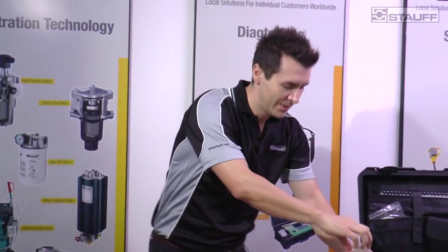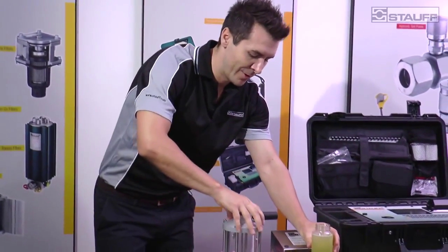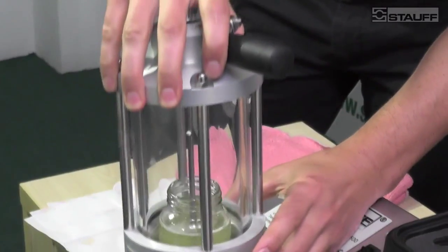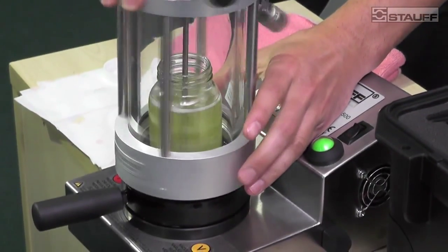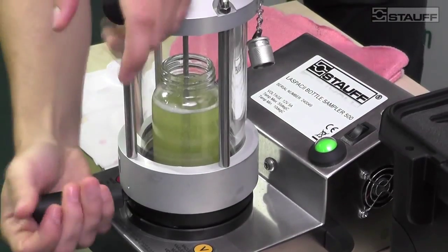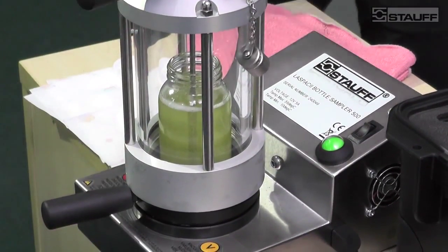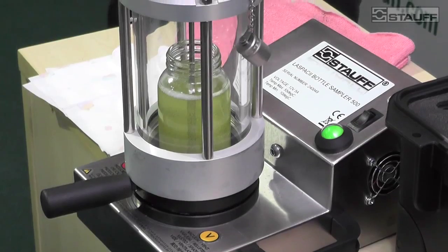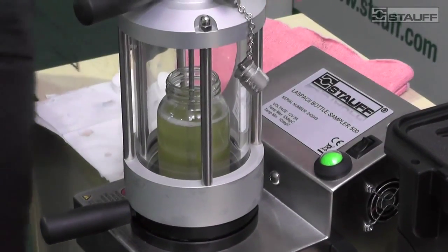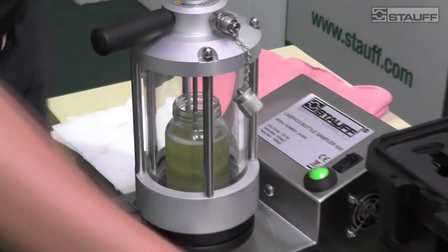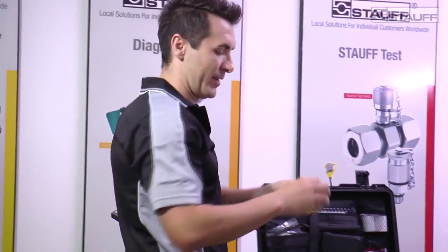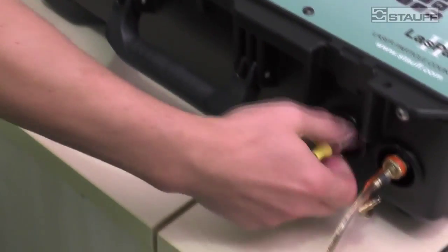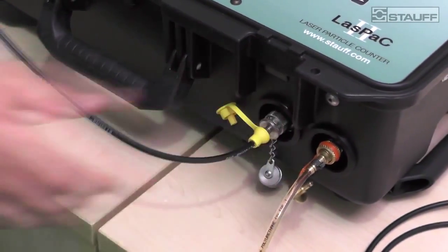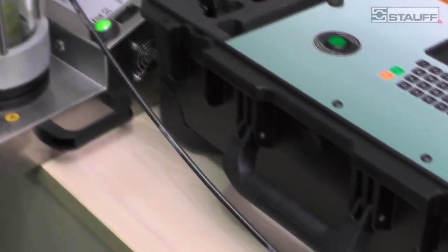And then put the bottle into the bottle sampler. And then very quickly close the lid. Make sure it's closed tight. So then we connect the hose. Ensure you connect the particle counter first, and then connect the other end to your bottle sampler.